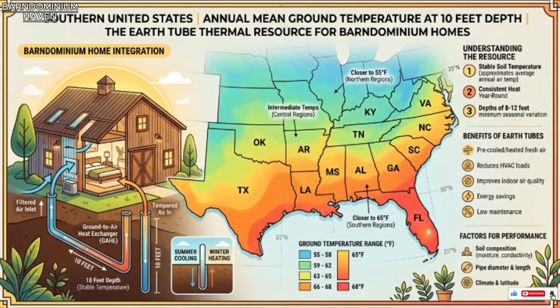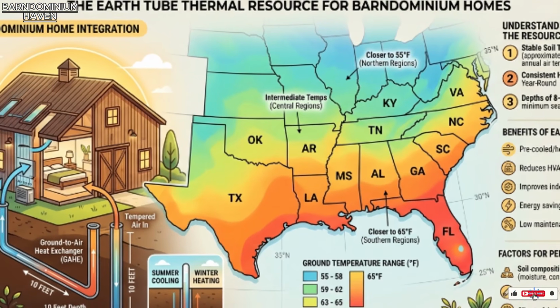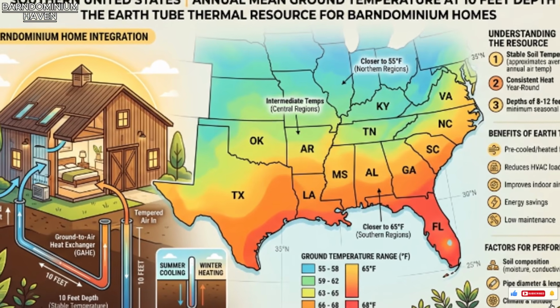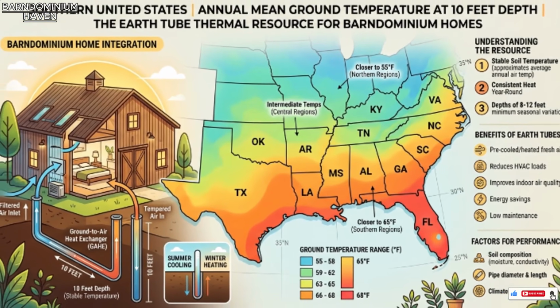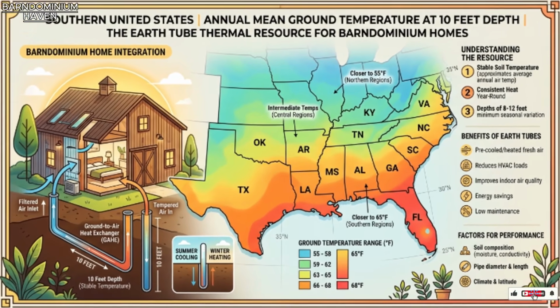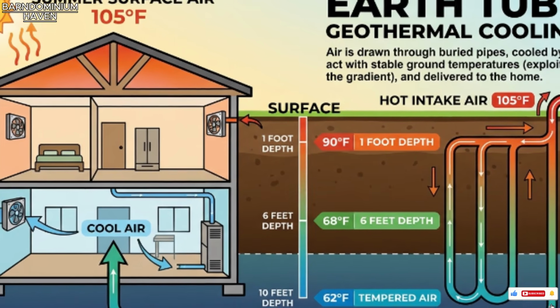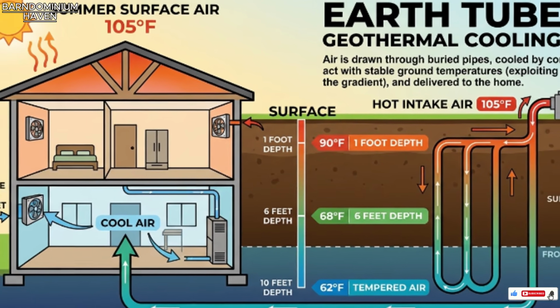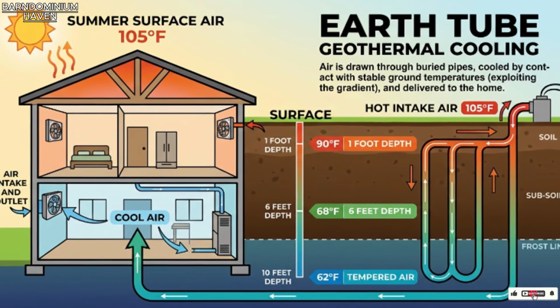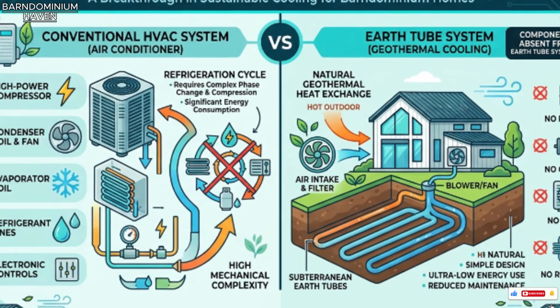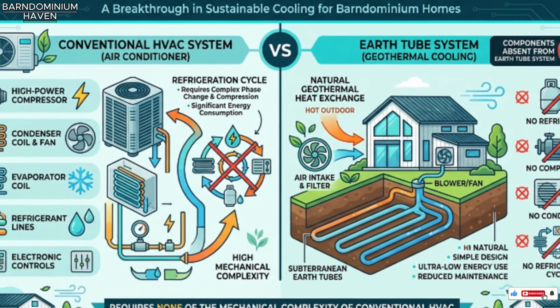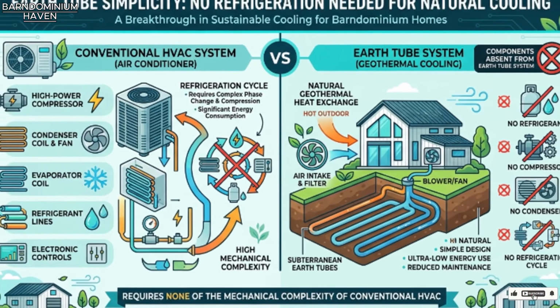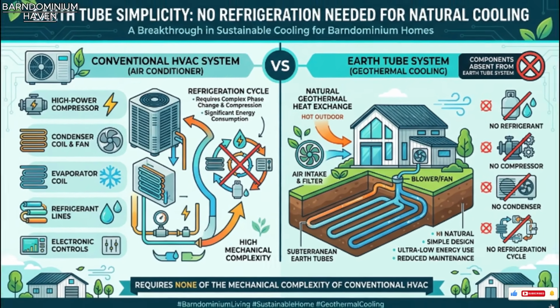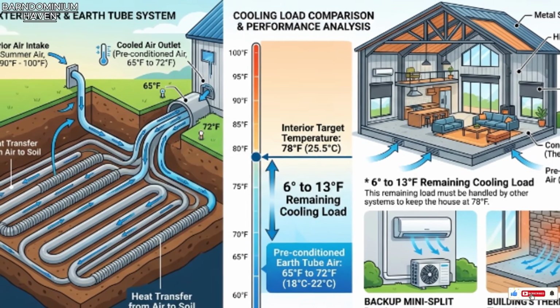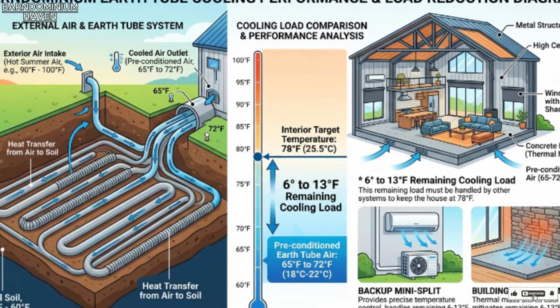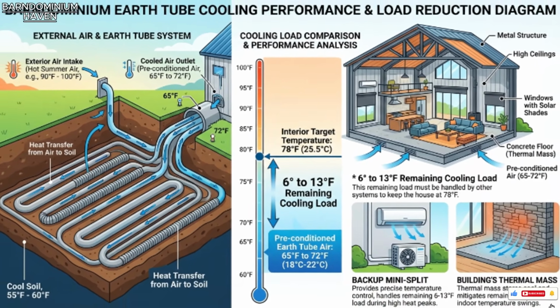The annual mean temperature of the specific location, which in the southern United States ranges from approximately 55 to 68 degrees Fahrenheit depending on latitude. This thermal stability is the earth tube's cooling resource. A cooling resource that requires no refrigerant, no compressor, no condenser, no refrigeration cycle. Just a pipe, a fan, and the understanding that the ground has been cooling air for free since before the first building was ever constructed above it.